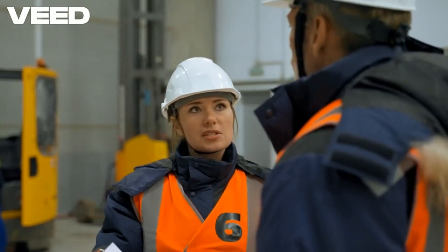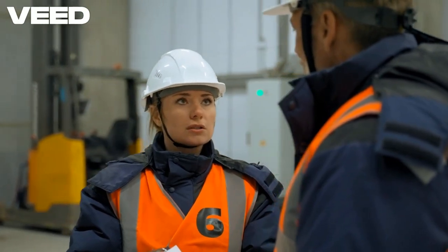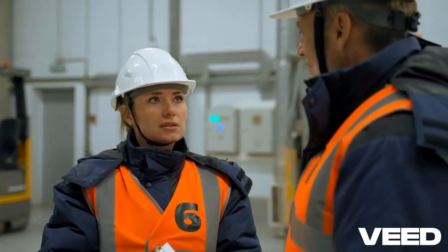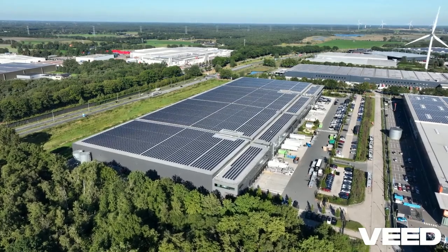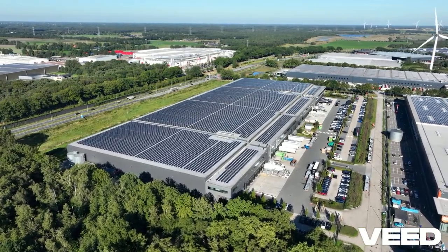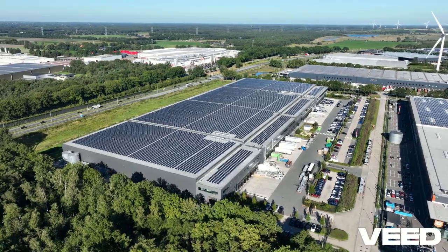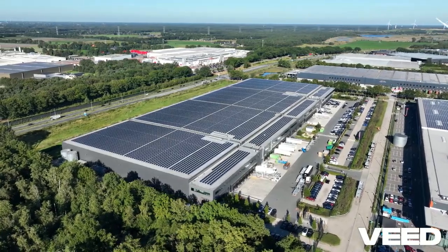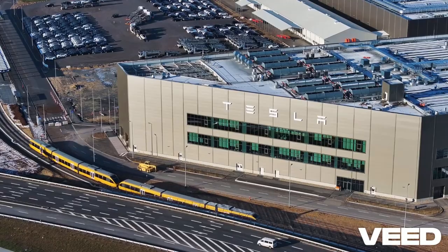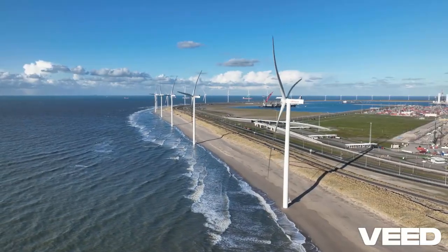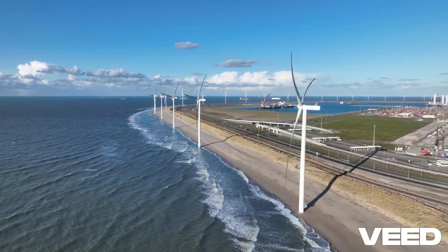Next up is power requirements. We have two main terms here: rated power and absorbed power. Rated power is the maximum amount of power equipment can handle under continuous operation. Exceeding this can lead to overheating and equipment failure. Absorbed power, on the other hand, is the real power consumed during actual use. Calculating absorbed power uses this formula: voltage x current x power factor. This helps in accurately sizing equipment and preventing system inefficiencies.